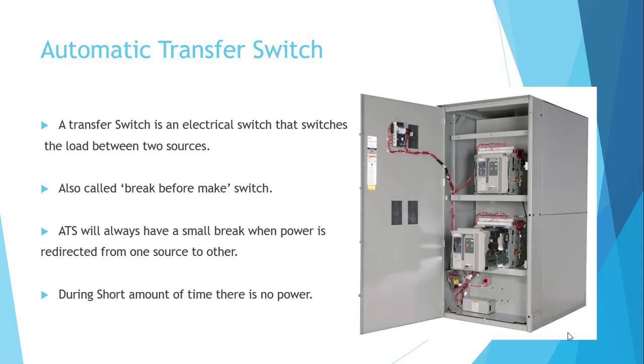That is, after the power grid fails and before the generator takes over, there is no power for that particular duration. But this is not a problem as the UPS will take care of it. The UPS uses its battery when there is a power loss due to the switchover, and therefore the IT load and the server rooms are still protected.